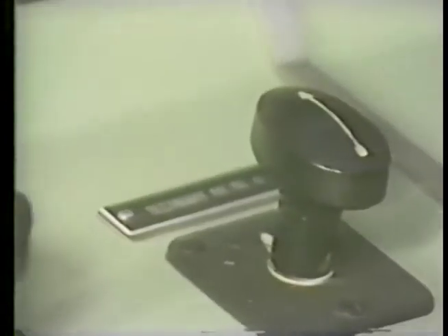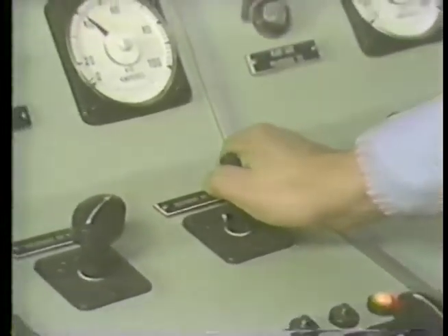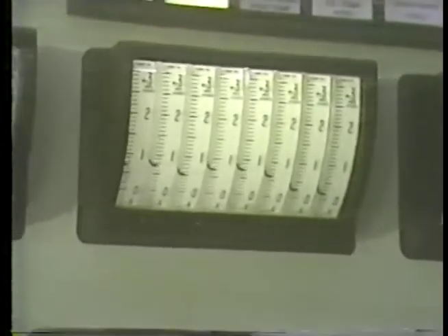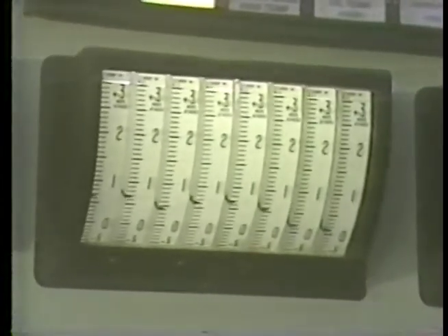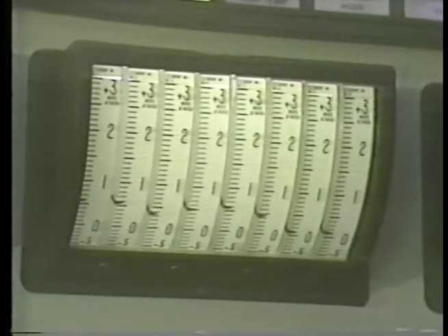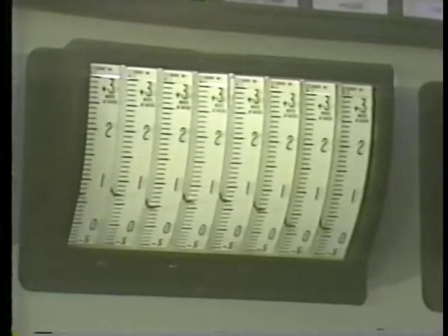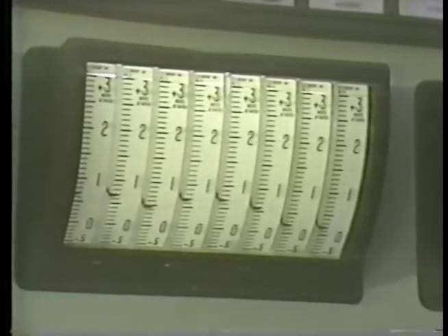The flow of air to the boiler is controlled by the positioning of dampers on the forced draft fans. Your plant's procedures will indicate the appropriate damper positions to provide the proper flow rate. Airflow to the boiler is monitored on these indicators in the control room. The fans are allowed to run for a designated period of time to purge the boiler of any combustibles that may be present. The amount of time necessary to purge the boiler is typically between 5 and 15 minutes.